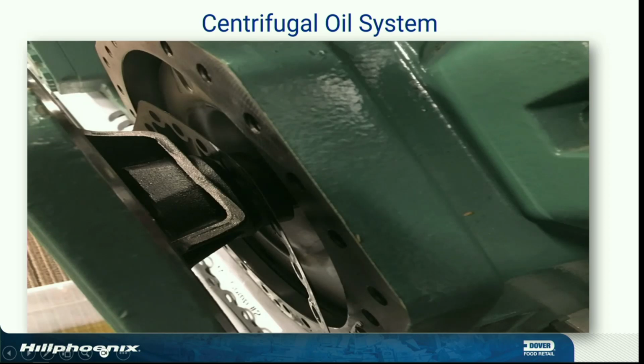Why go to a slinger instead of a pump? Don't need a pump. That's how they design these compressors. We only have pumps on the 40s and the 50 horses. Copeland's the same way. Why don't K-bodies have slingers? The old K-bodies had slingers. The old K-bodies were very, very hardy, weren't they? They're 40, 50 years old out there. So it's a good design. But anyway, you'll see the oil slings around, it collects in this cup, and then it's sucked literally down into the shaft as the shaft's turning, all right?